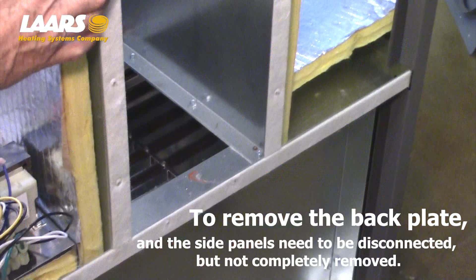On the flue collection box, there are going to be 2 screws for the flue collection. That's not holding this back panel, but it will be in your way when you go to pull the back panel out. So remove all of the back screws on the flue collection.